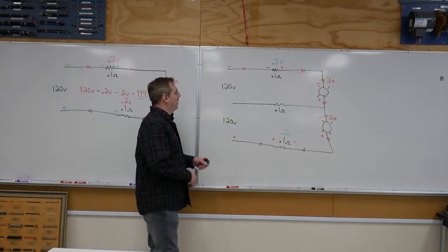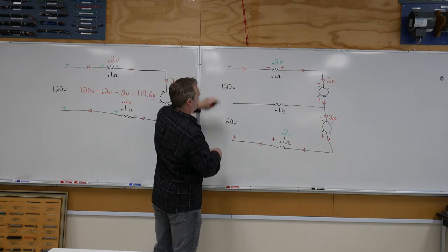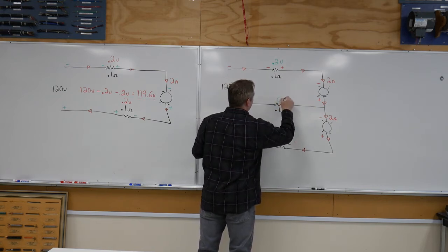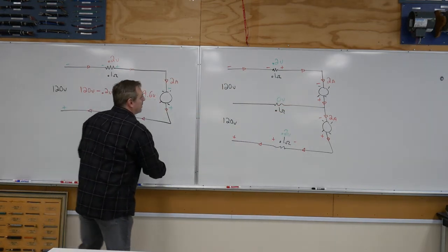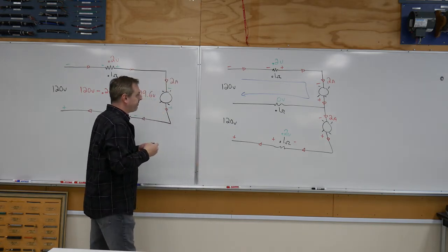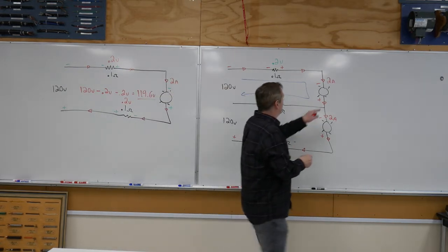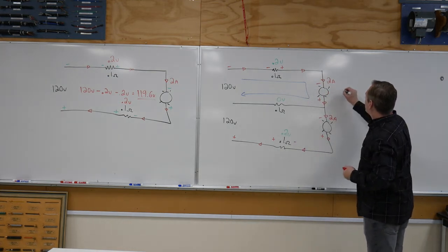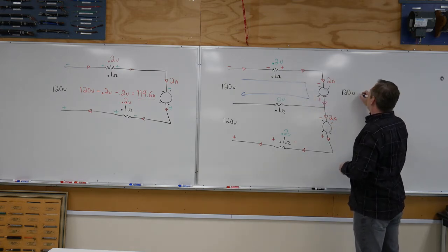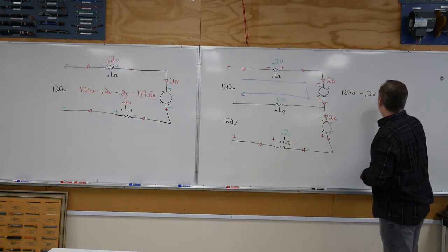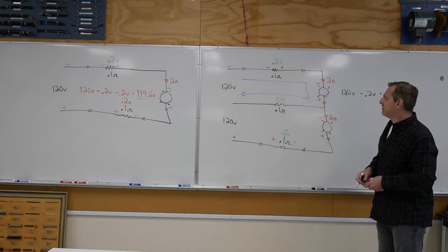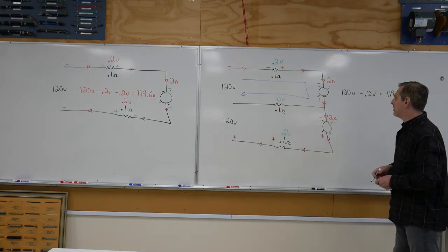So we look at our entire source here. In this circumstance, we've got 0 volts here. And if we followed, almost mimicking a current path this way, even though we have nothing on that, this voltage out here would start at 120 volts, and then we're going to subtract our 0.2 volts, and that gives us 119.8 volts. The reason why I didn't go any further is because we know our neutral's balanced. If there was current on that neutral, we'd have to take one more step, and I'll do that in a second.